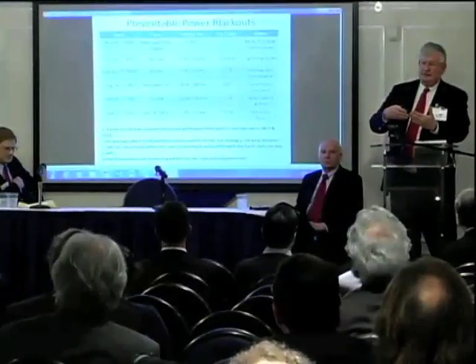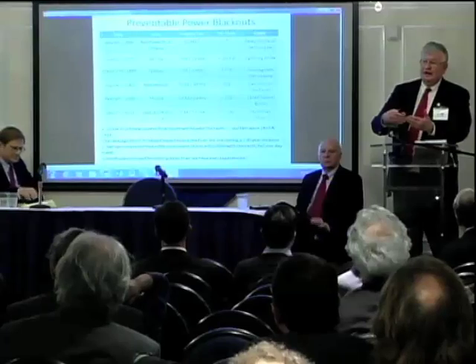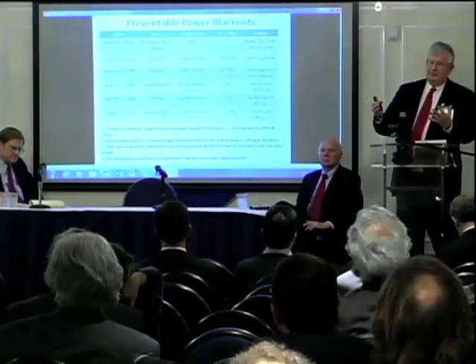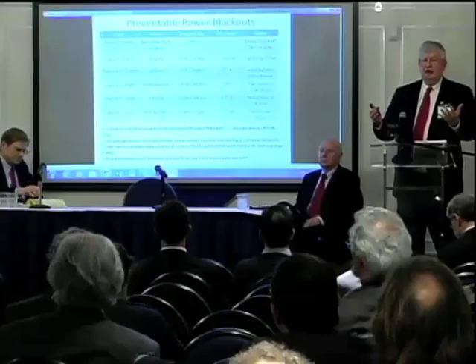So with that, one of the first things we've heard from NERC is that one of the biggest risks to the grid is grid instability caused by a GMD event because of half-cycle saturation on the transformers. And it could be a blackout, but some utilities have said to us, well, a blackout will happen before there's any damage to equipment. So let's take that as item number one.